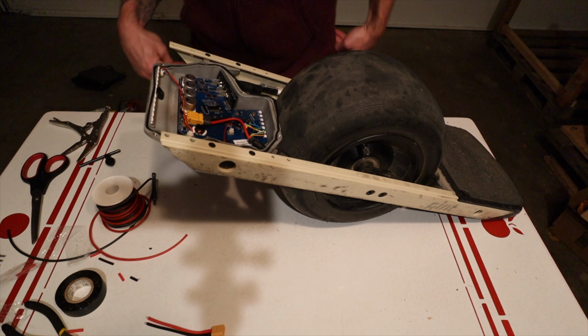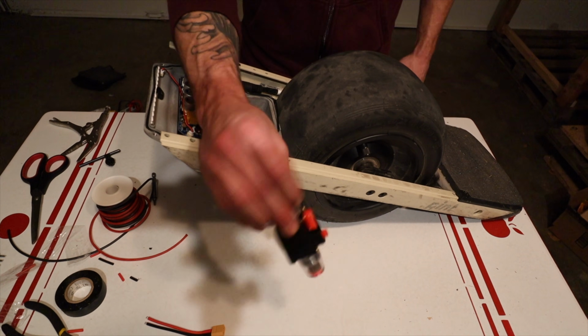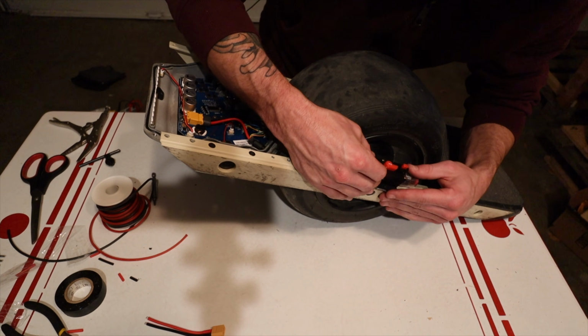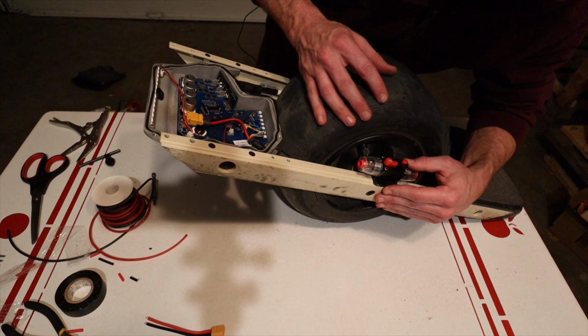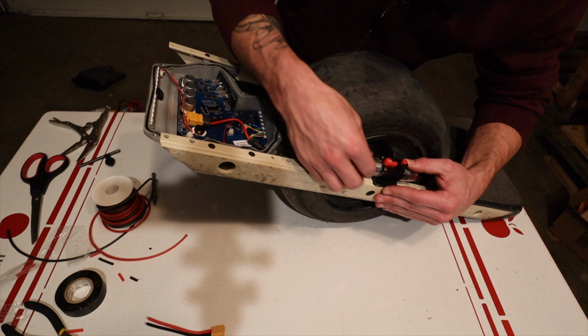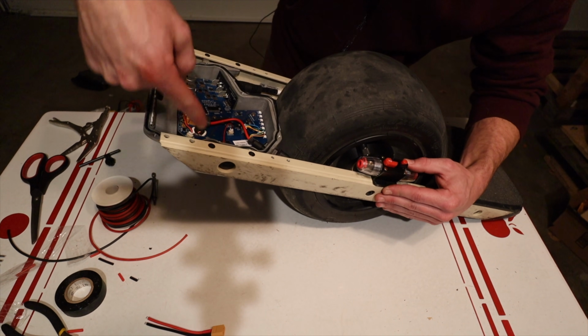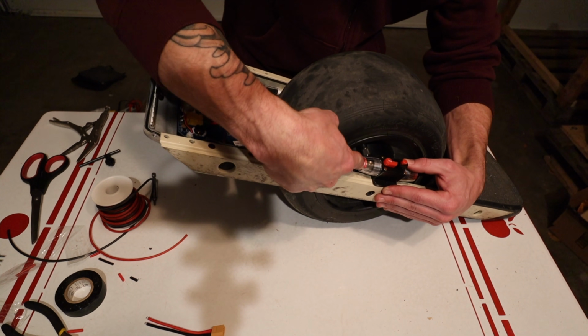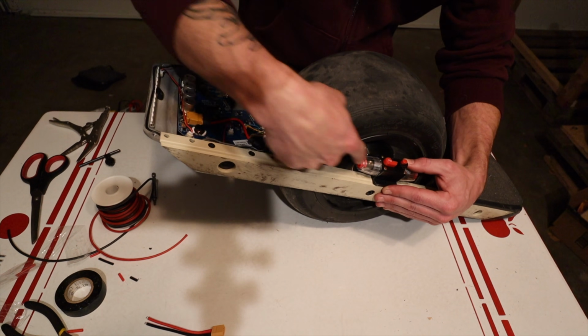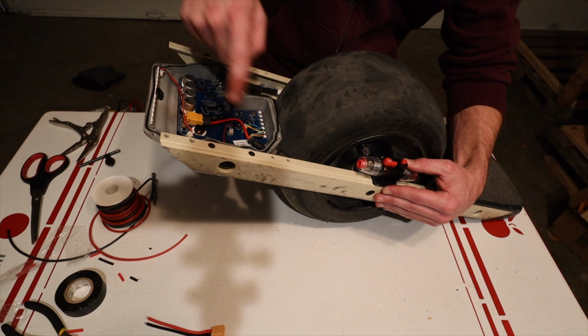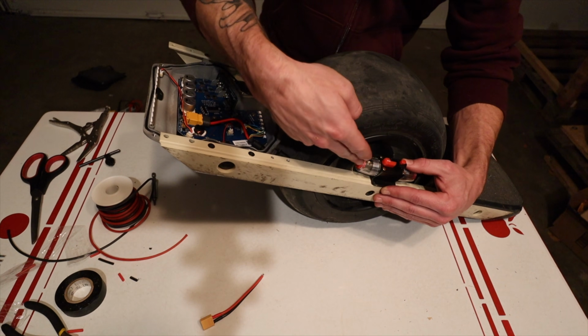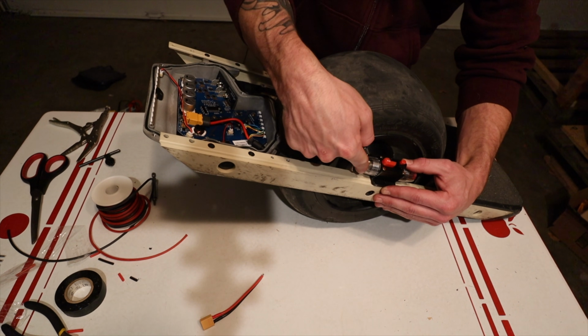We're going to take the circuit breaker and mount it right here. It seems really tight, but it will fit. We're going to run the cord from the power line all the way into here—that's the first connection. The ground, the black line, just runs straight to the XT connection since you don't have to run that into a circuit breaker. You only run one wire, the power line.